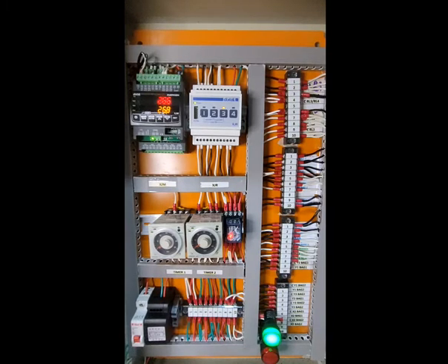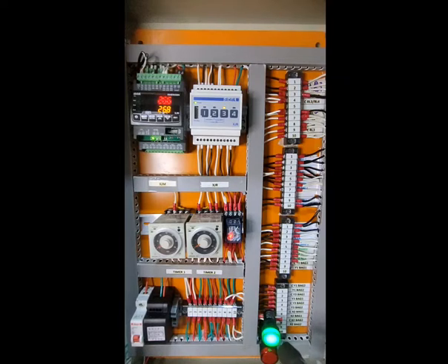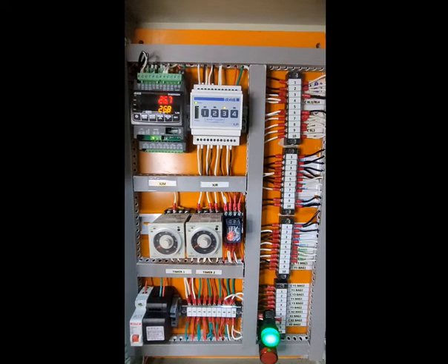I set the alarm to 31, so whenever the temperature reaches 31 degrees C, there will be a room temperature problem, the temperature gets too hot. Okay, so we are just waiting for a minute or two to test the changeover of the AC units via time. Okay, so as you notice, it flips from AC unit 1 to AC unit 2, which followed via time.